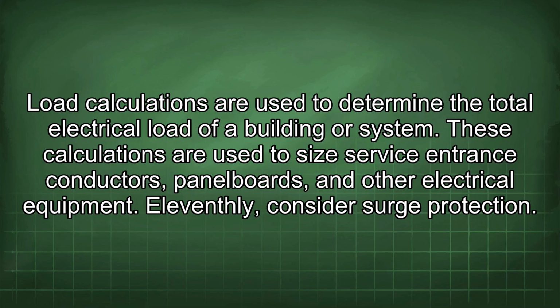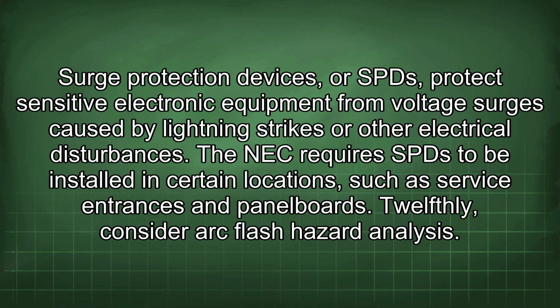11thly, consider surge protection. Surge protection devices, or SPDs, protect sensitive electronic equipment from voltage surges caused by lightning strikes or other electrical disturbances. The NEC requires SPDs to be installed in certain locations, such as service entrances and panel boards. 12thly, consider arc flash hazard analysis.